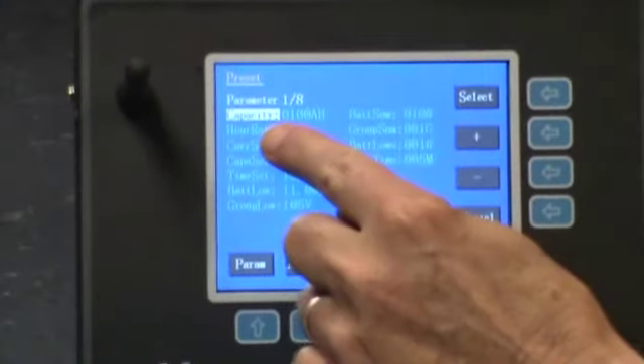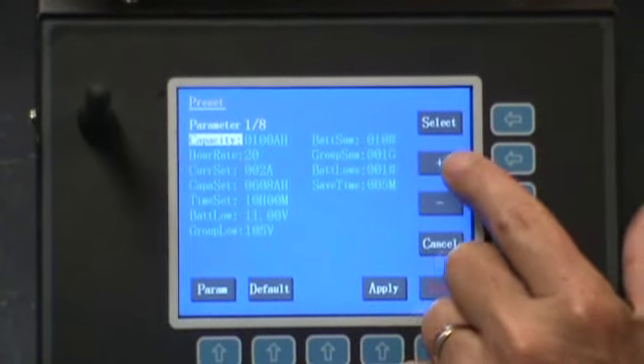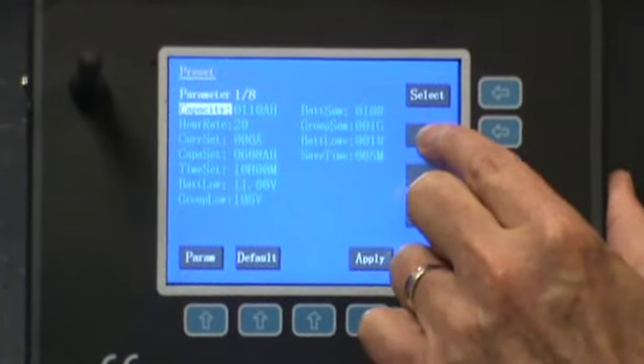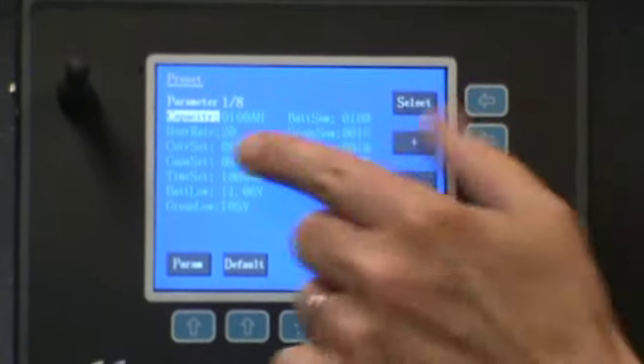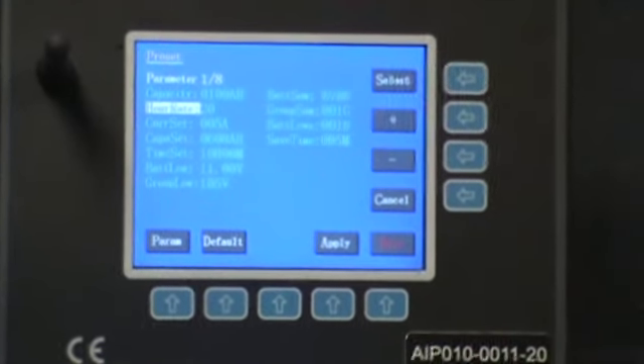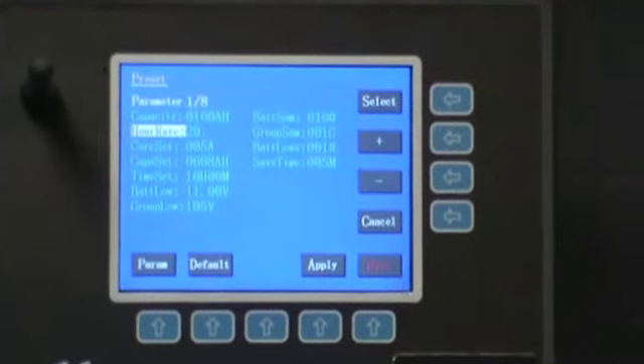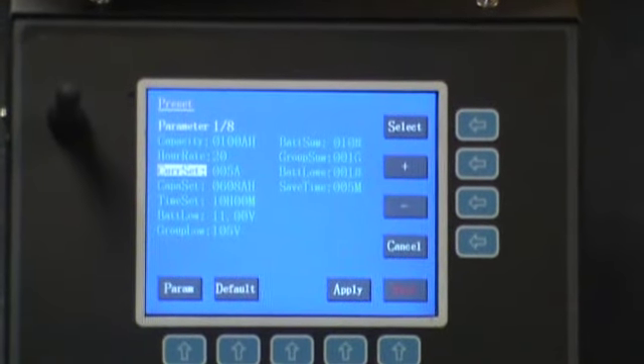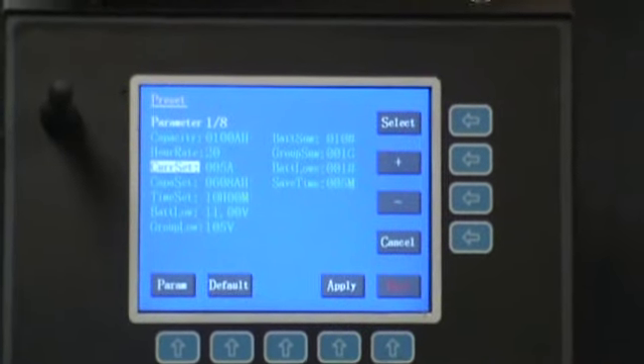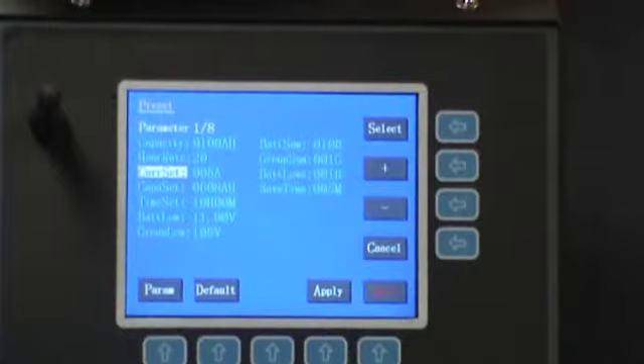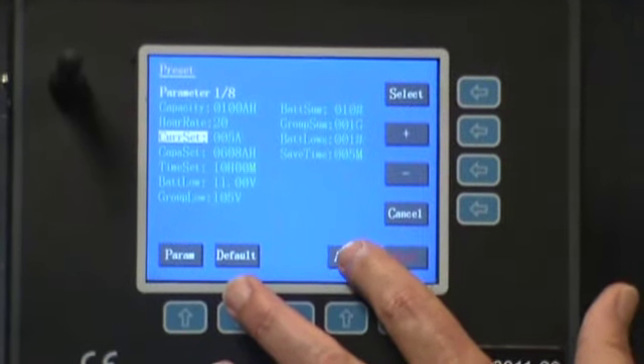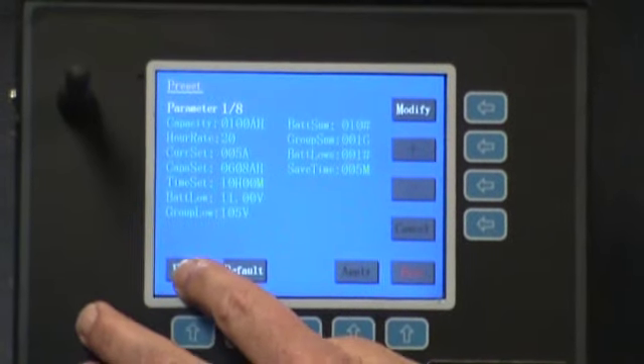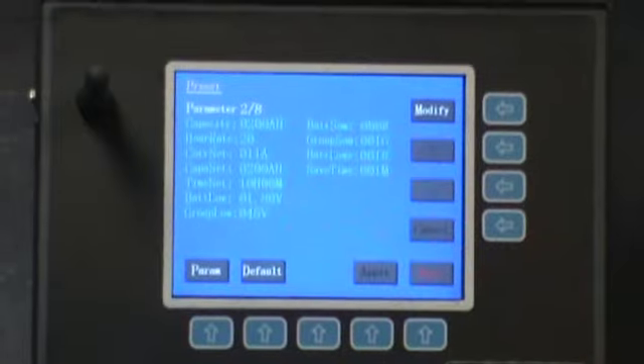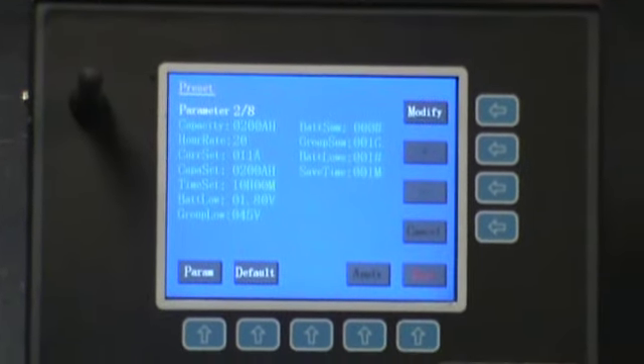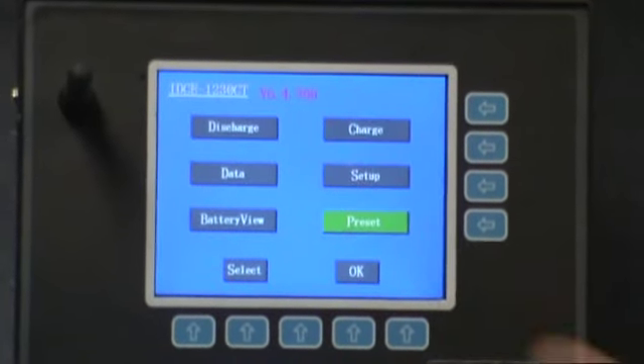If you wanted to change any of the parameters, you would hit modify, and then it immediately highlights the capacity. If you want to change capacity, you've got a plus or minus button here. I can run it up or down. If I want to move down to the next selection, I say select. It moves down to the hour rate, I can change what that is, and so on. You can move it down to current set. Once you've selected what you want, you hit apply, and that saves it under that parameter. Now if we want to change parameters, we go to parameter 2, and we can set up whatever we want, all the way up to 8. When you're done, you would exit.